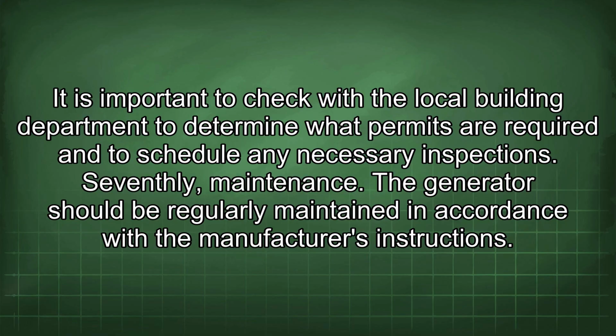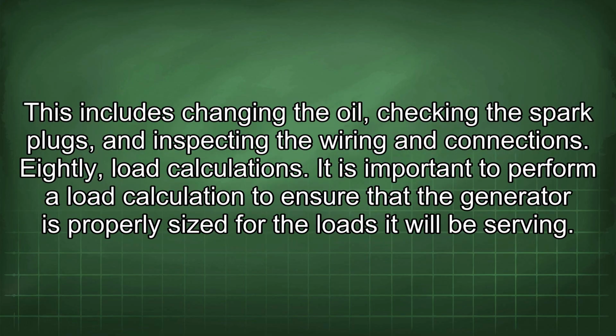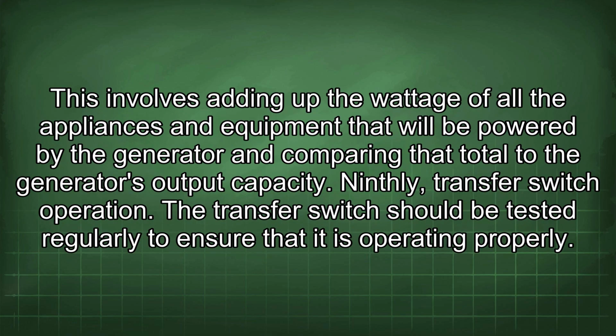necessary inspections. Seventhly, maintenance. The generator should be regularly maintained in accordance with the manufacturer's instructions. This includes changing the oil, checking the spark plugs, and inspecting the wiring and connections. Eighthly, load calculations. It is important to perform a load calculation to ensure that the generator is properly sized for the loads it will be serving. This involves adding up the wattage of all the appliances and equipment that will be powered by the generator and comparing that total to the generator's output capacity.